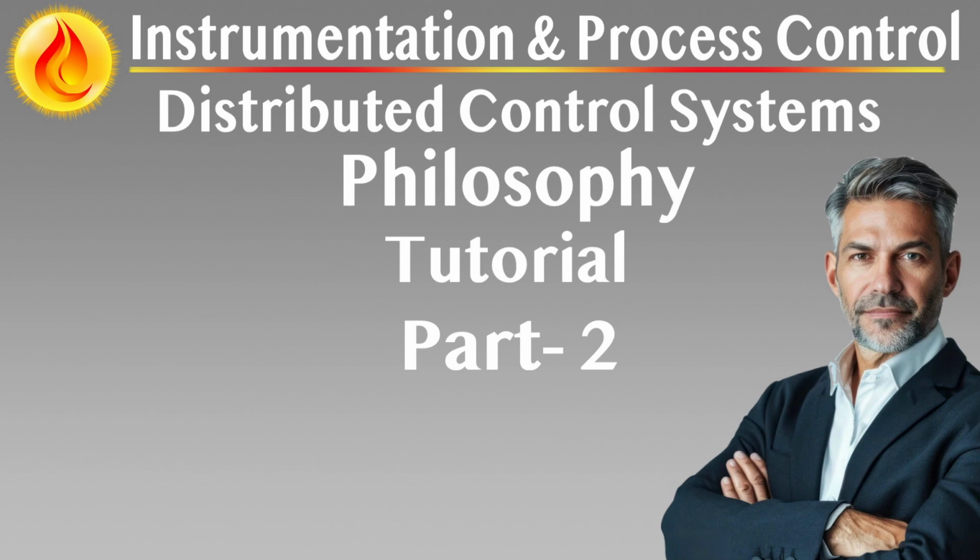Manual initiation. Manual emergency stops are triggered via hardwired latching push buttons, tactile key switches, or explosion-proof devices in field and control room locations. All manual initiators are monitored for integrity, e.g., line break detection, and are immune to DCS software interference. Remote and secure control. Remote shutdown capabilities are enabled through authenticated interfaces with secure protocols. Cyber-hardened edge gateways restrict access based on role, geofencing, and emergency override procedures.